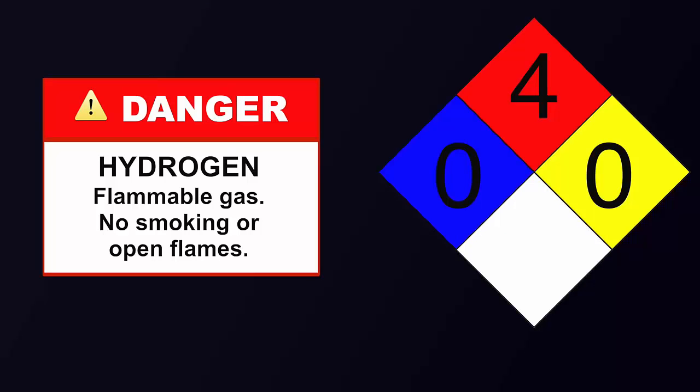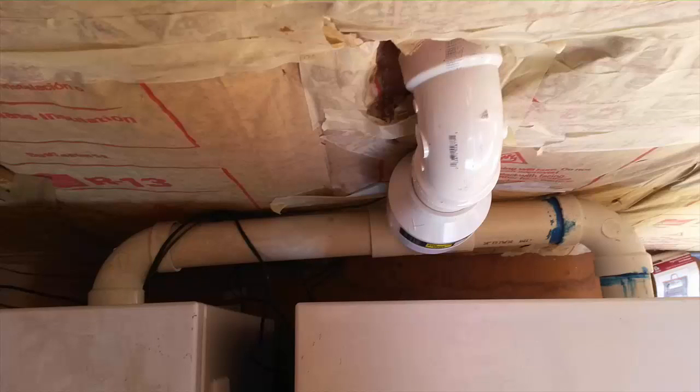The most important is that many battery types emit explosive hydrogen gas when charging and discharging. This is most common with lead-acid batteries. This gas should be automatically vented outdoors by the system, whether actively with a fan or passively. But fans can fail and vent tubes can become clogged by insects and other debris. Firefighters should always assume an explosive atmosphere could be present inside any battery room or enclosure.